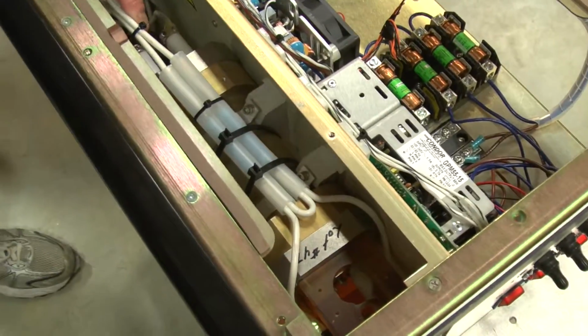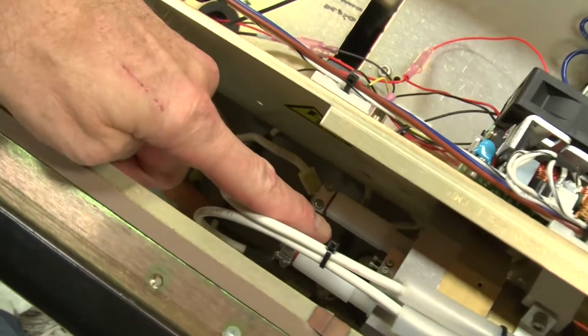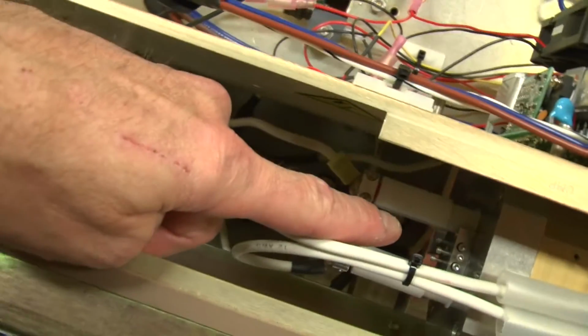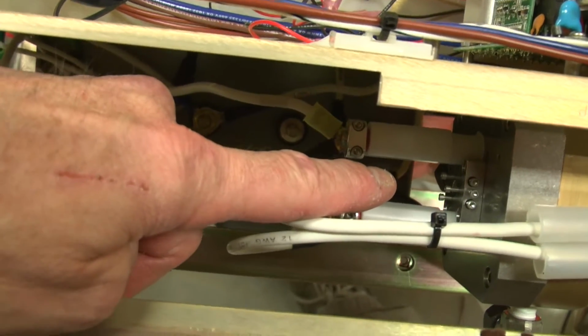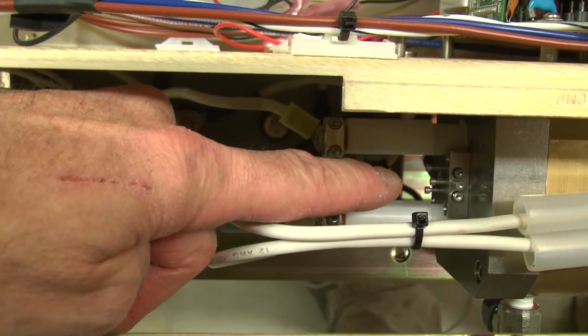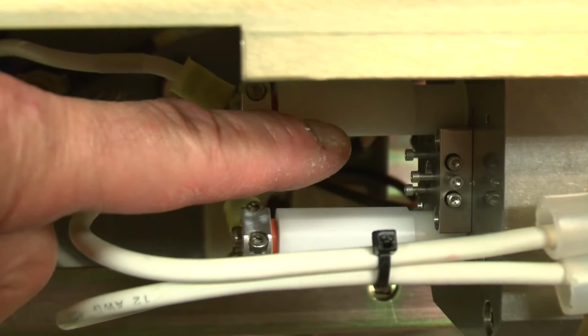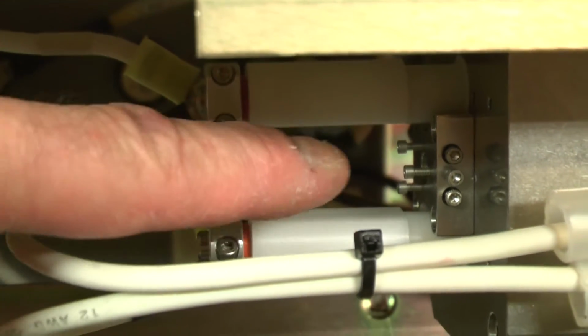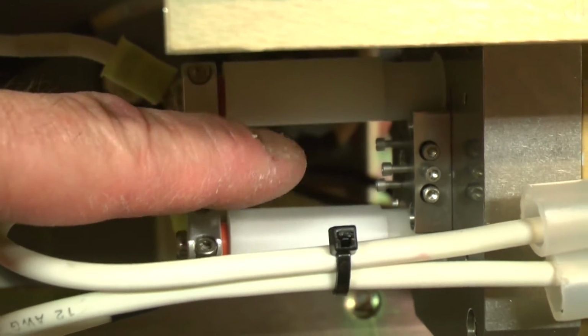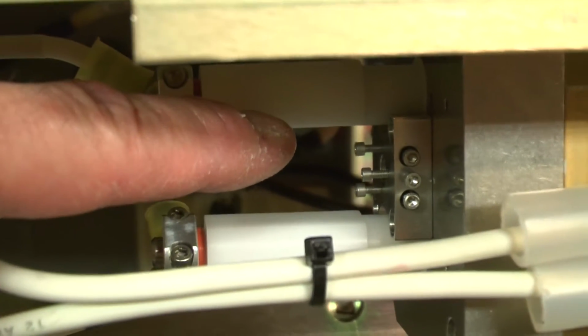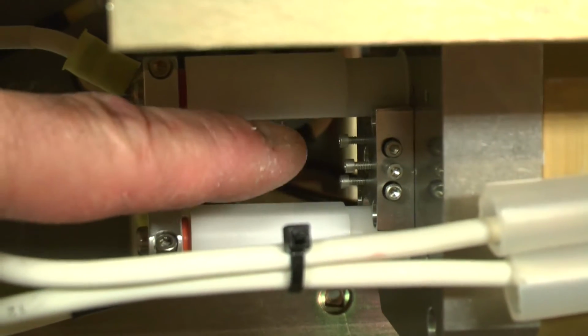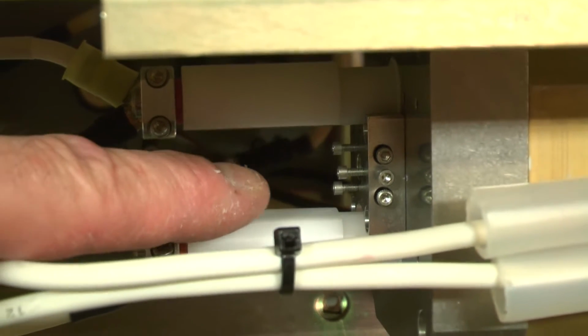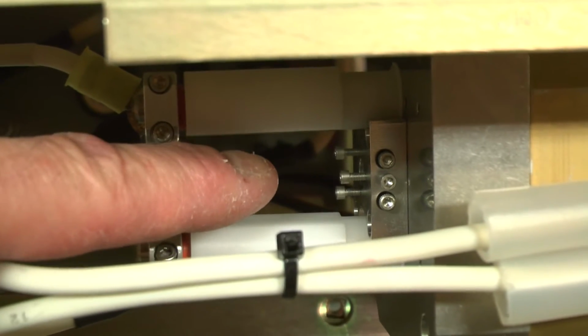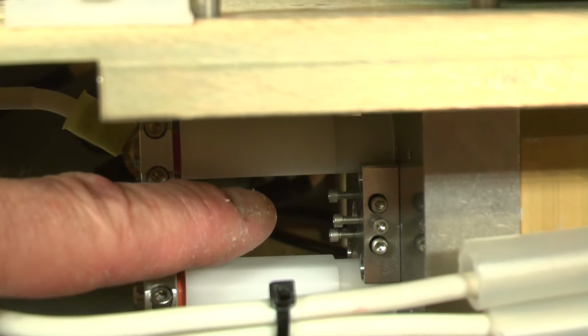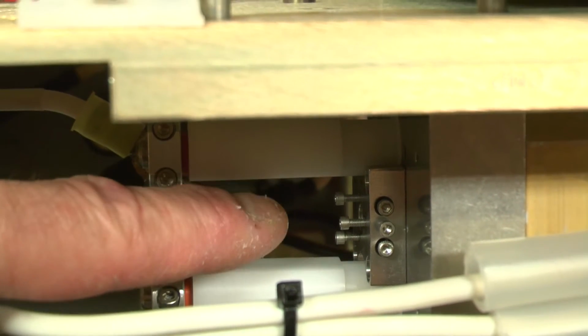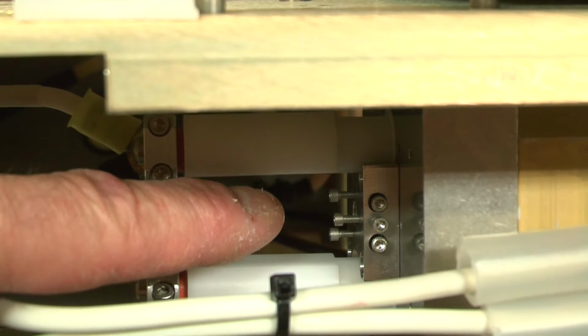You can probably get a good view over here by that little metal housing. The mirrors, which are plano, are placed in small indentations in this outer stainless steel block and then held to seal the cavity by a little silicon O-ring that's underneath the mirror. And then these 3 set screws push on a little ring to actually compress the O-ring and align the optics. Kind of funky in terms of alignment, but nevertheless, it works, and it certainly is compact and convenient.